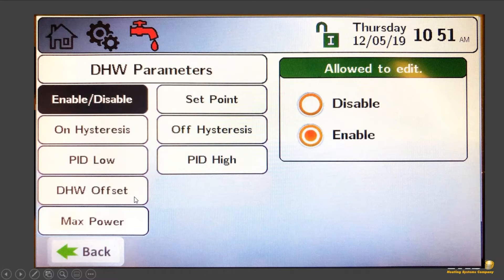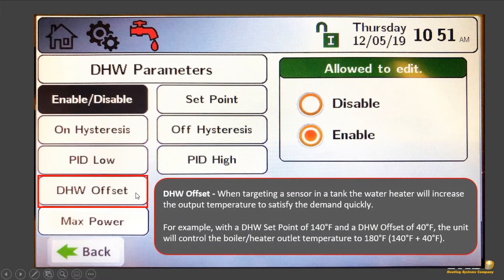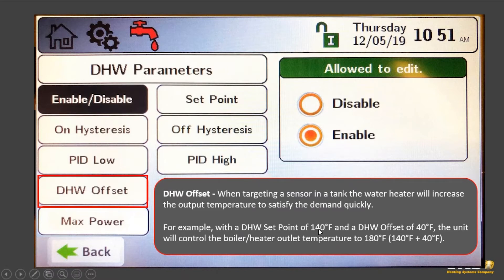Something else to talk about here is DHW offset. When you're using a sensor in a tank, you want the outlet temperature of the boiler or water heater to be higher than your set point. In an example of 140 degrees, you want at least 150, 160, or 170 degrees exiting the water heater — because you want to satisfy that tank quickly. If you only deliver 140 degrees to a 140-degree set point tank, it could take forever. In our manual example, a 140-degree set point with a 40-degree offset results in a heater outlet temperature of 180 degrees, satisfying the demand efficiently.